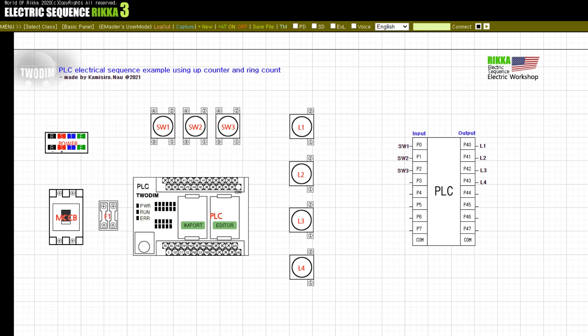However, if all lamps do not light up after SW1 input, SW2 input is not received. After all lamps are turned on, the PLC ladder is configured so that SW2 push button can be used. When SW3 push button is pressed once, the L4 lamp turns on and off at one-second intervals. When SW3 push button is input again, L4 lamp operation stops.